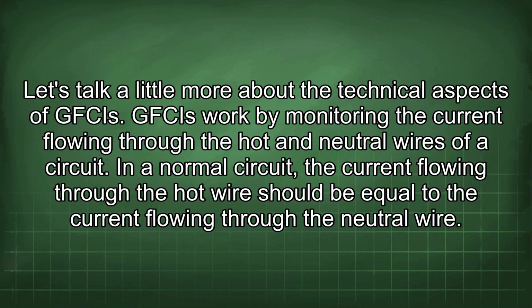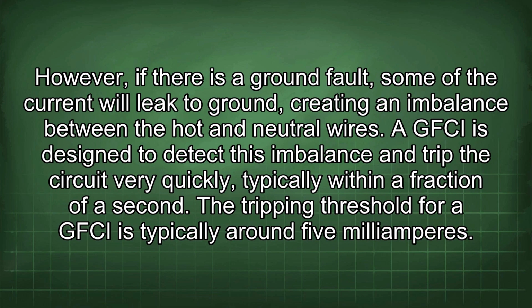Let's talk a little more about the technical aspects of GFCIs. GFCIs work by monitoring the current flowing through the hot and neutral wires of a circuit. In a normal circuit, the current flowing through the hot wire should be equal to the current flowing through the neutral wire. However, if there is a ground fault, some of the current will leak to ground, creating an imbalance between the hot and neutral wires. A GFCI is designed to detect this imbalance and trip the circuit very quickly, typically within a fraction of a second. The tripping threshold for a GFCI is typically around 5 mA.